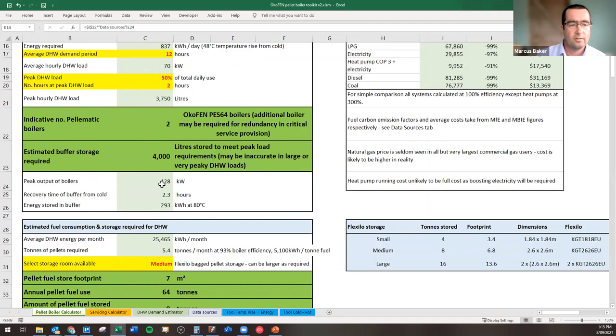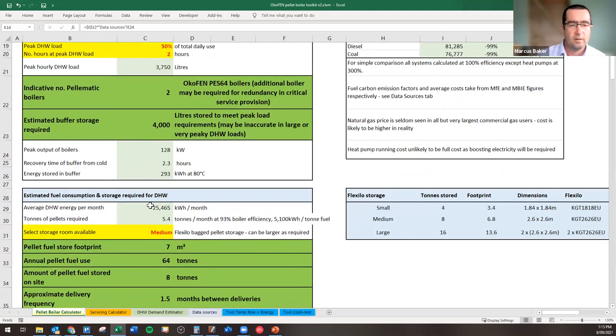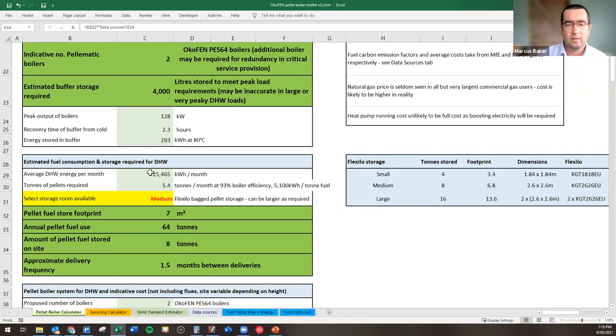So boilers, peak output, recovery time of the buffer from cold, energy in the buffer, what we reckon it would be a month. They again, just averaged out. These aren't exacts, but also then how many tons of pellets would be required a month. And you can choose, if you've got very little room, this is how much space it's going to take up, and this is the time between deliveries.